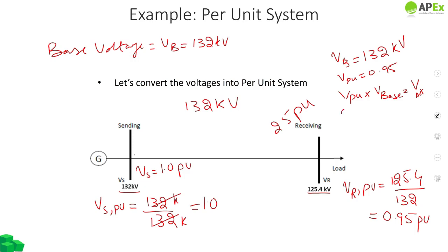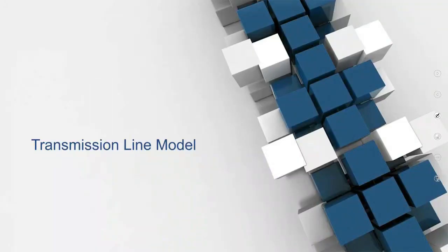So multiply 0.95 with 132 kV, which is our base voltage, we would get 125.4, which is essentially the receiving end voltage. So the purpose of this was to show that given the base value of any quantity, we can convert a per unit value into the actual value and any actual value into a per unit value. So now we'll move ahead.